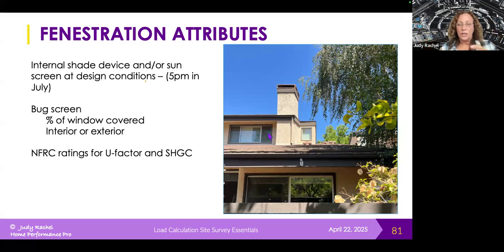There are tables in the Manual J procedure that give defaults for the U factor and solar heat gain coefficient when we can only describe a window. In that case, Manual J and the software pull those values from the description tables. But if we actually have the U factors and solar heat gain coefficients, we're much better off entering those real numbers, since fixed windows have different solar heat gain and U factors than operable windows, and sliding glass doors and French doors differ as well. So don't assume one value applies to all windows.